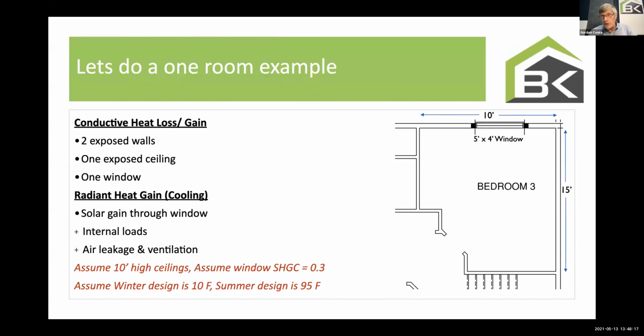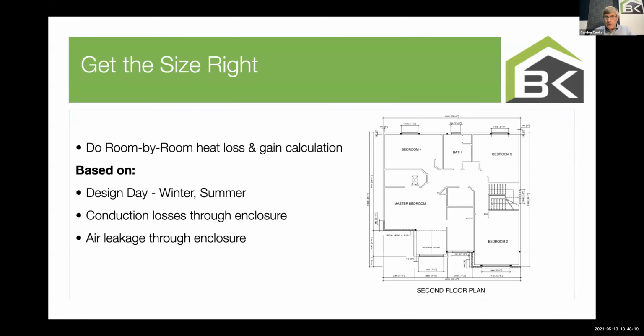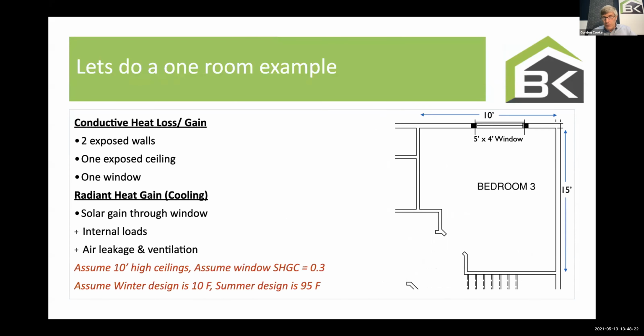So I'm just going to give you a little quick example. You see that bedroom, top right, bedroom 3: a 5x4 window, a 10-foot wall, a 15-foot wall, which means I've got 150 square feet of attic space. You get the idea. It's got 2 exposed walls. It's got 1 exposed ceiling. It's got 1 window. And on the cooling side, in addition to that, we need to understand the solar gain through that window, plus some internal loads. So I'd have to think about the people in that bedroom. Plus, I'd have to think about air leakage and ventilation in both of those cases.